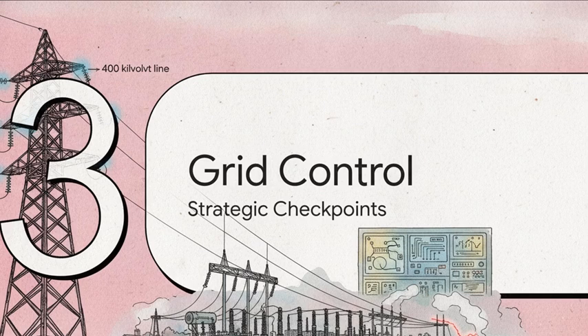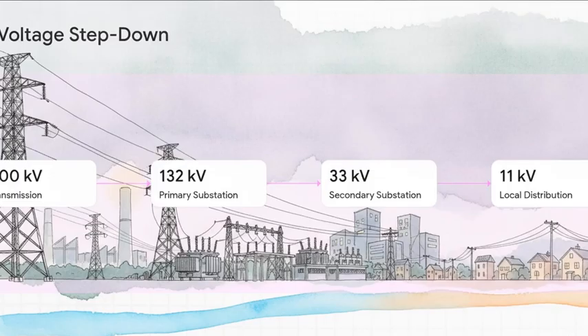Which brings us to part 3, substations and grid control, the strategic checkpoints of our journey. Think of substations as the off-ramps of our high-voltage highway. We don't just suddenly drop the voltage all at once, it works in a progressive scale-down arc. We take that incredibly dangerous 400 kilovolt transmission line and step it down to a 132 kilovolt primary substation for a whole region, then down to 33 kilovolts for a secondary city substation, and finally down to 11 kilovolts for local distribution. This gradual reduction is absolutely essential to ensure stability and safety, as all this power moves closer to where people actually live.